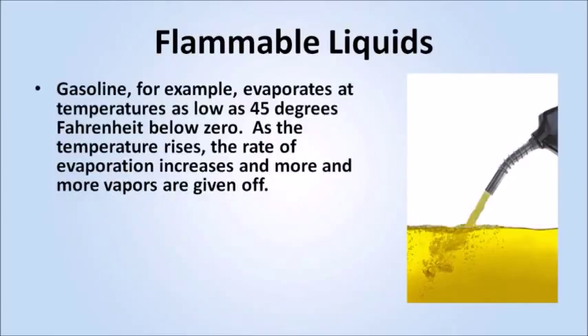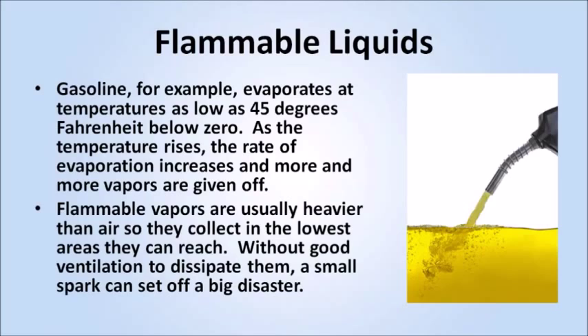Gasoline, for example, evaporates at temperatures as low as 45 degrees Fahrenheit below zero. As the temperature rises, the rate of evaporation increases and more and more vapors are given off. Flammable vapors are usually heavier than air, so they collect in the lowest areas they can reach. Without good ventilation to dissipate them, a small spark can set off a big disaster.